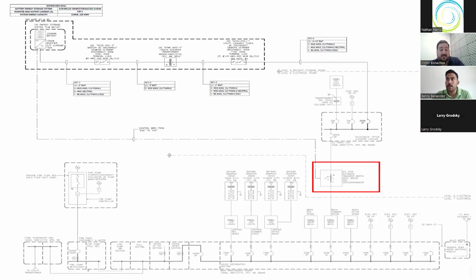But in this case, all power sources are offline, and the only one that could potentially turn back online, which is the inverter, can't because it's still tied to the utility. So there's no way to actuate that switch in this case to provide any sort of isolation for those loads. You're kind of just stuck in the connected position permanently. Which is a great example of, again, people misapplying ATSs into applications where an isolation device, an isolation switch, interconnect switch, is really the correct solution to get the functionality that they are looking for.